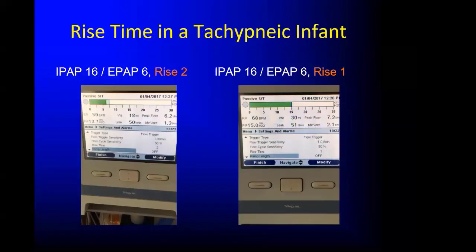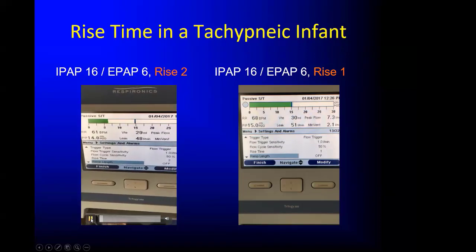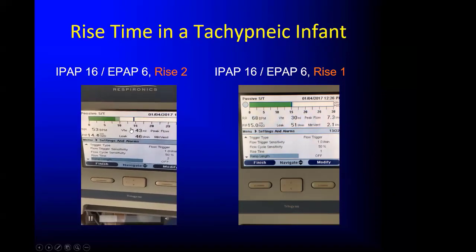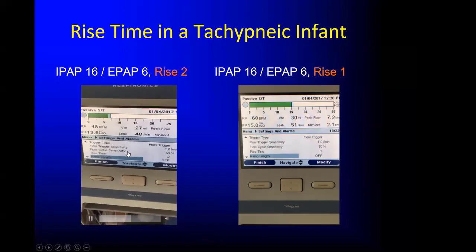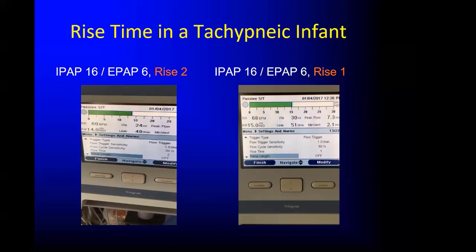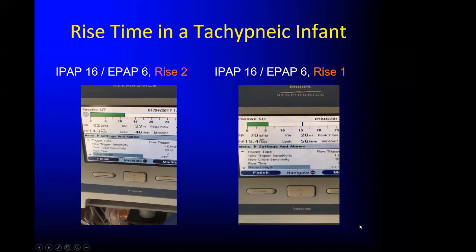And so here, in fact, was a baby with SMA who was being supported, and the set inspiratory pressure was 16, and the rise was set at 2. I want you to notice that this baby's inspiratory pressure is never getting to 16 centimeters of water. You think, this baby is getting a pretty good inspiratory effort, but in fact, it's pretty much down there at around 14 centimeters at best. The only change we made was to shorten the rise so we hit the pressure faster. Because this baby is so tachypneic, you really need to hit that peak pressure faster. And now look, routinely you're hitting a peak pressure of 16 centimeters. In fact, the tidal volumes were larger as a result of this, and so we improved this baby's ventilation.